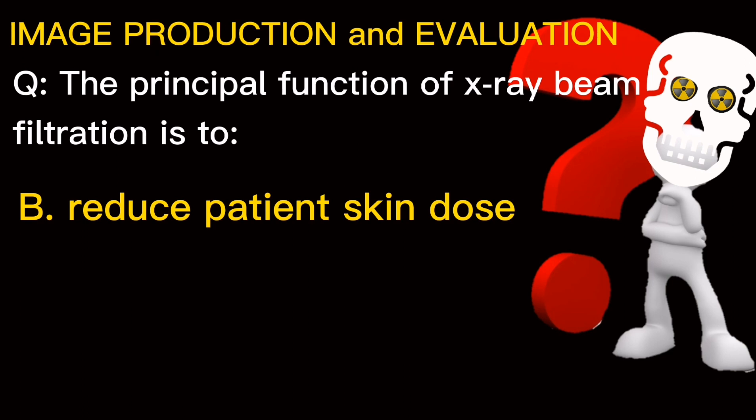Filters, usually made of aluminum, are used in radiography to reduce patient dose by removing this low energy radiation, resulting in an X-ray beam of higher average energy. Total filtration is composed of inherent filtration plus added filtration. X-ray tubes operating above 70 kVp must have a minimum filtration of 2.5 mm of aluminum or its equivalent.